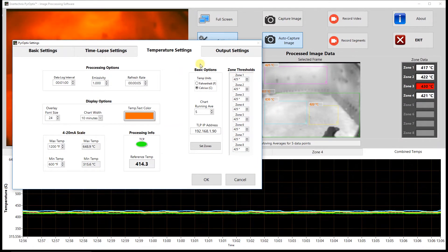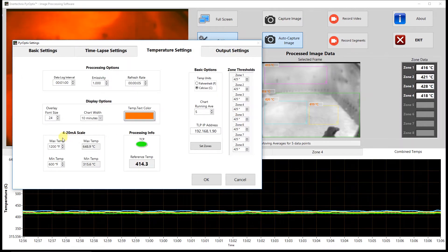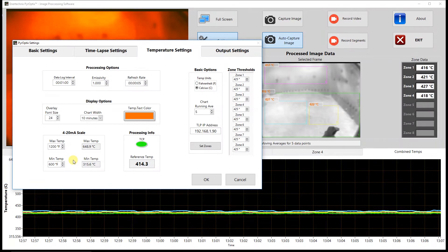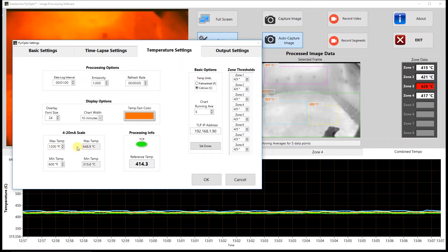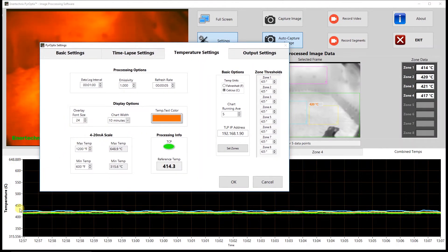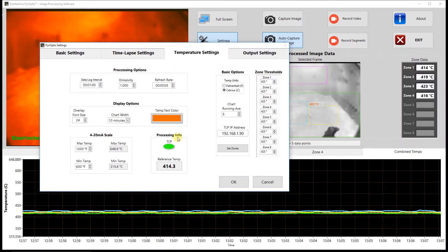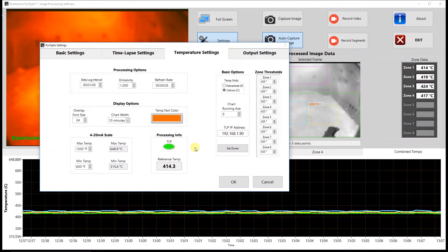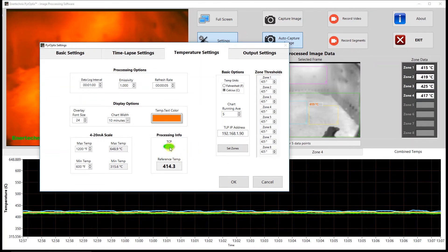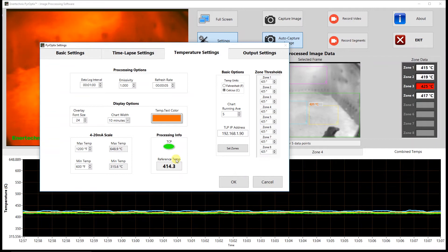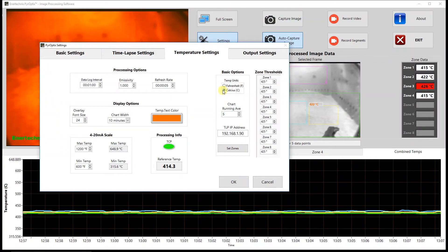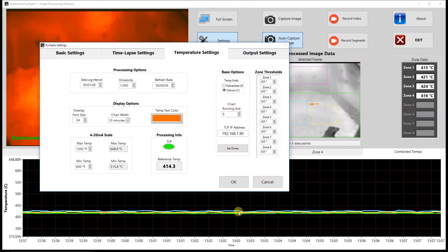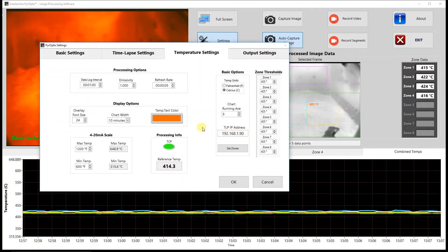Below that, we have the 4 to 20 milliamp scale. As you saw on the output settings page, we have a 4 to 20 milliamp output option. On the scale right now, the low end — the 4 milliamp section — would be 600°F or 315°C, and the top end or 20 milliamp would be 1200°F or 648.9°C. This can be adjusted, and it also affects the y-axis or temperature scale on the chart on the front panel. Moving over to processing info, we have the TCP connection, which is just the connection between the module where we read the data from — green means we are connected, red means we are not. Reference temperature is the actual reference temperature we get from that data, and that is the temperature we use for processing. Under basic options, we have temperature units, where you can choose between Fahrenheit or Celsius. And we have chart running average, which is the running average for the data displayed on the chart seen on the front panel. TLP IP address is the IP address of the module that we get our temperature information from.